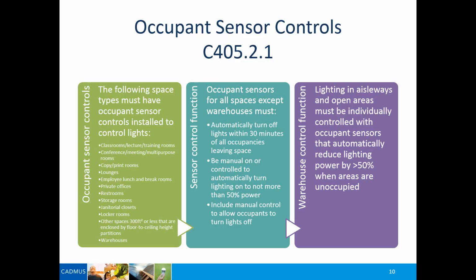When you start looking at the green box, the occupancy sensor controls and where they're required, you're going to notice the types of spaces where lights are typically left on. For example, a private office: someone has their lights on in there, they step out, they forget to turn the lights off, and lights can be left on in private offices quite a long time. Also locker rooms, restrooms, lounges. There's always the old adage and the old story about having an occupancy sensor in the restroom and someone's going to the bathroom and the light turns off. There are different types of occupancy sensors that you can get that will make sure that isn't going to happen, but it always makes for a great story. Warehouses are also required to have occupancy sensor controls. So you'll see a whole shopping list of occupancy types that will actually be required to install occupancy sensors.